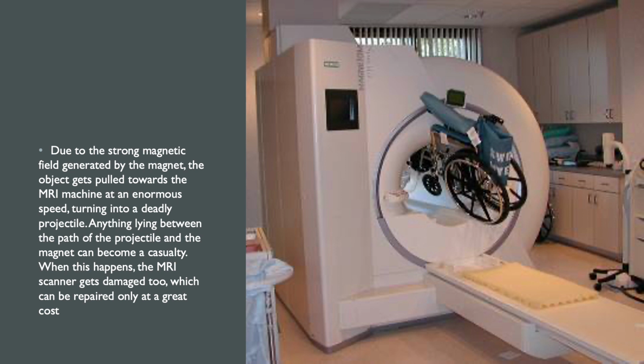Anything lying between the path of the projectile and the MRI can become a casualty. When this happens, the MRI scanner gets damaged, which can be repaired only at a great cost. Please note, objects that do not appear to contain any metal may have ferromagnetic metal inside, so always take extra precaution.